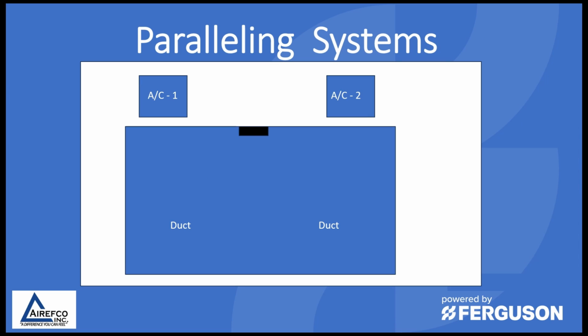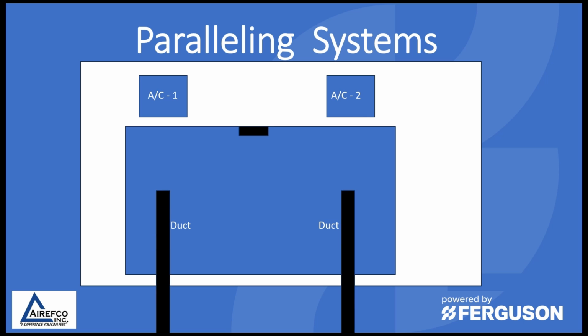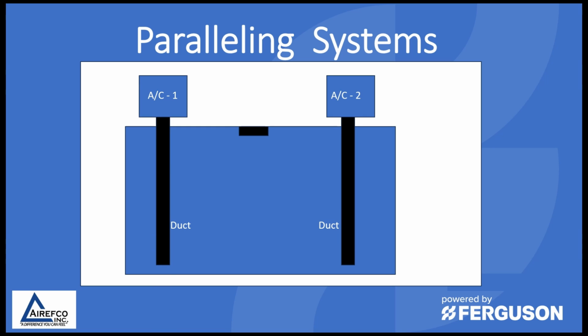In paralleling systems, you're going to have two AC or heat pump systems, and you'll run the ductwork down the sides of the sanctuary ceiling, and the two systems will be controlled by a single thermostat. By doing this, you can have the capacity that you need for the building, and it will be controlled by one thermostat, so you will not have systems fighting each other to control the space.